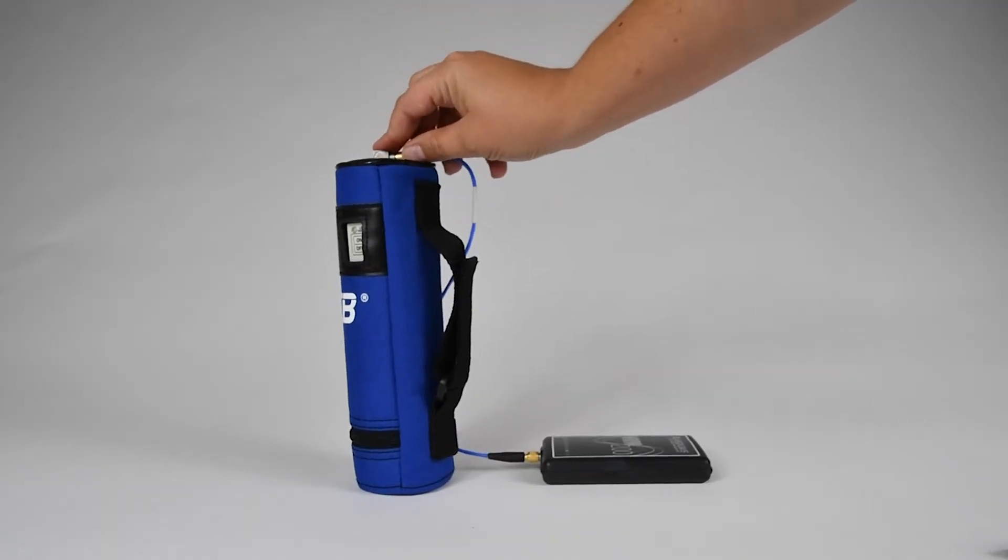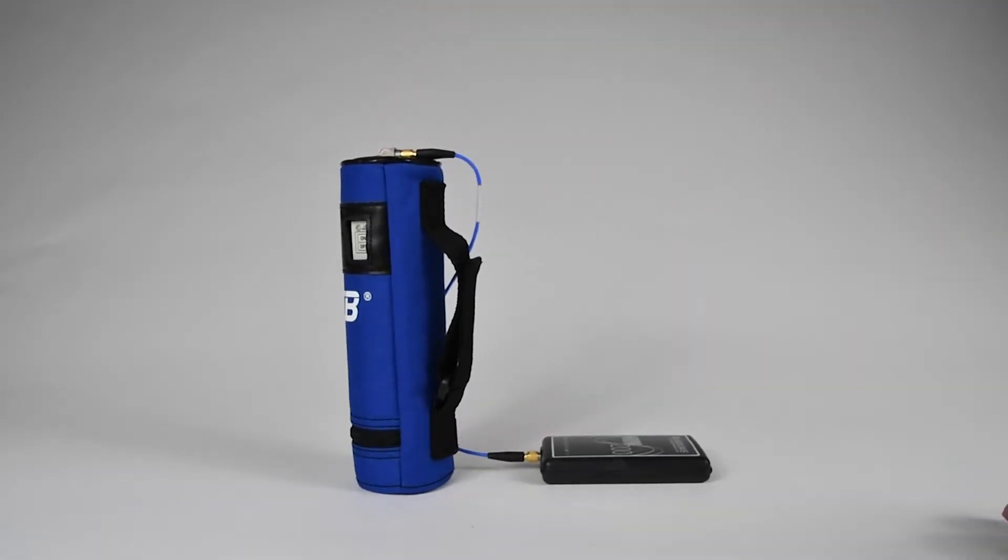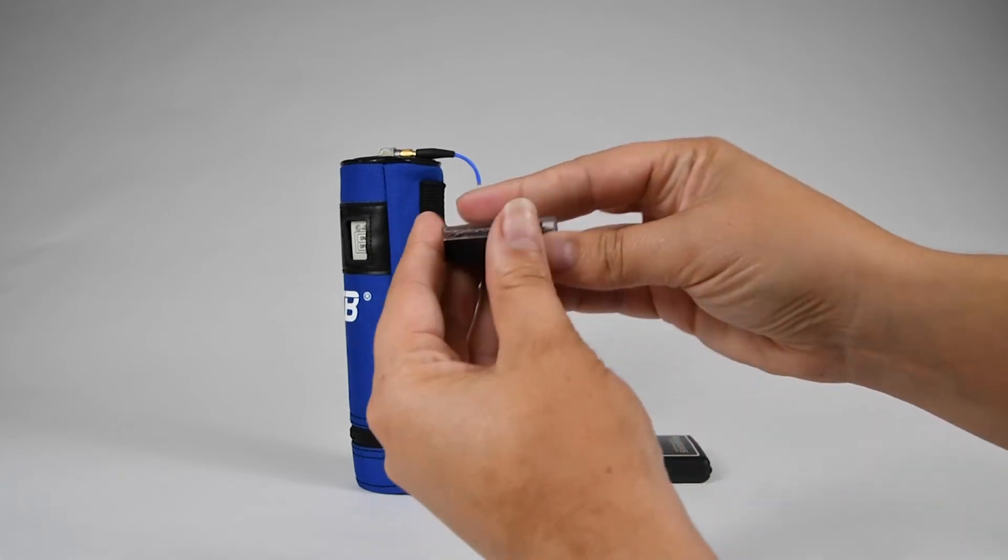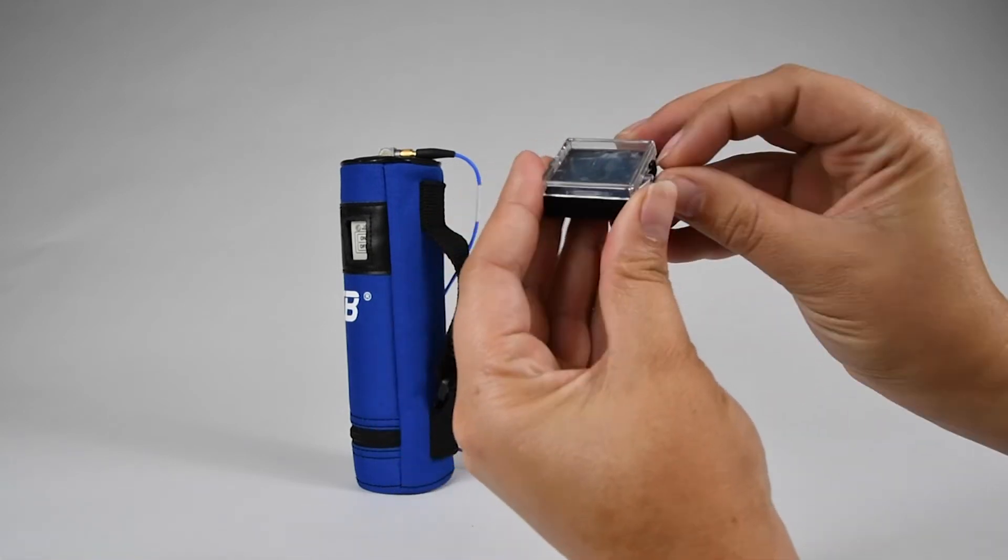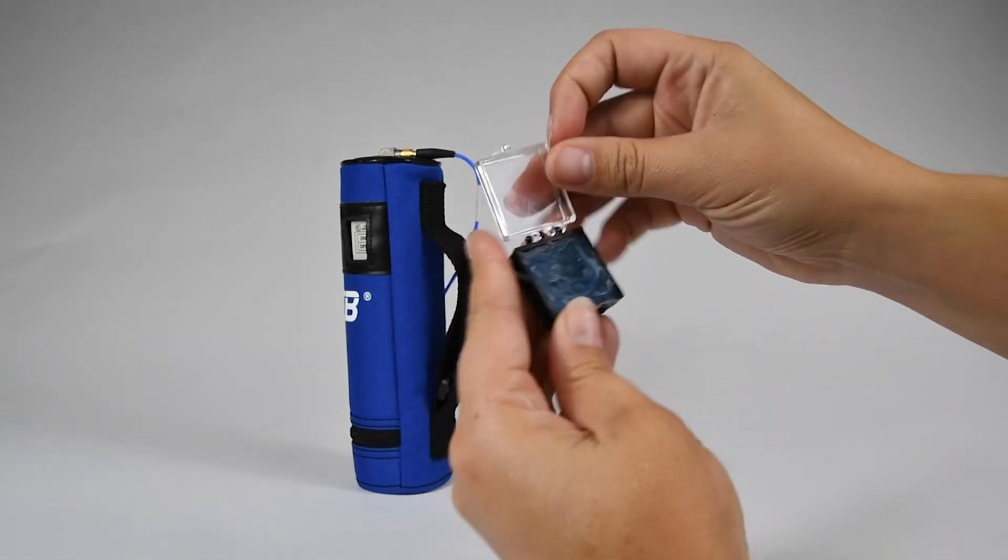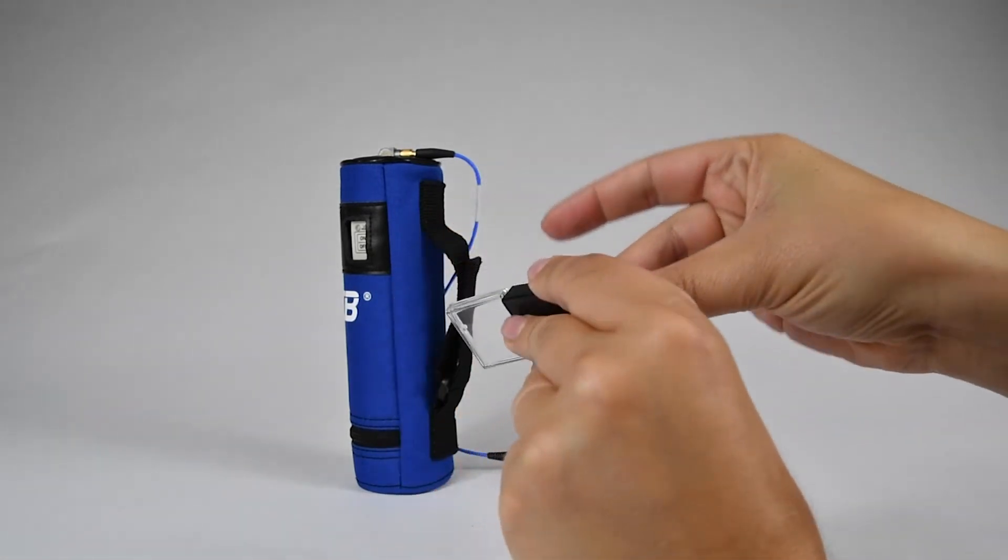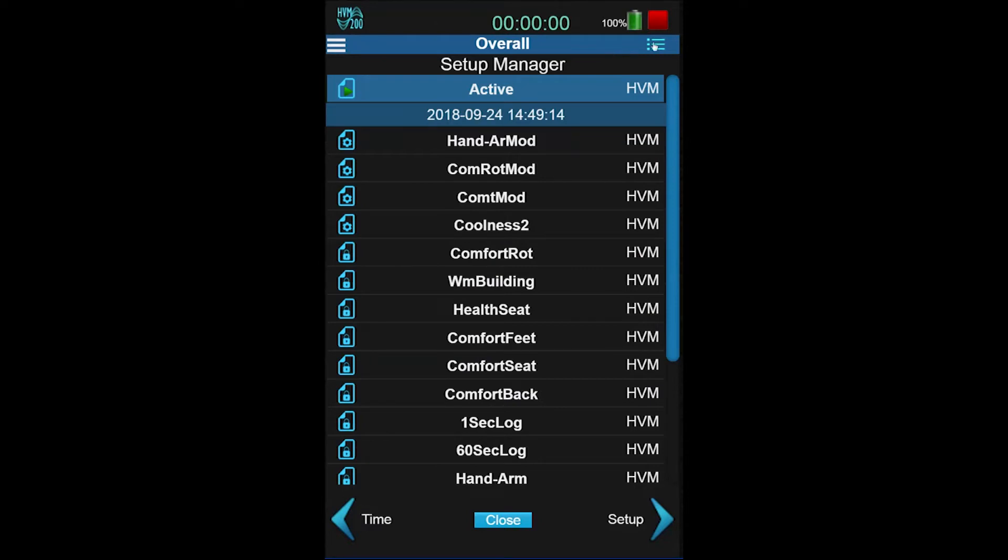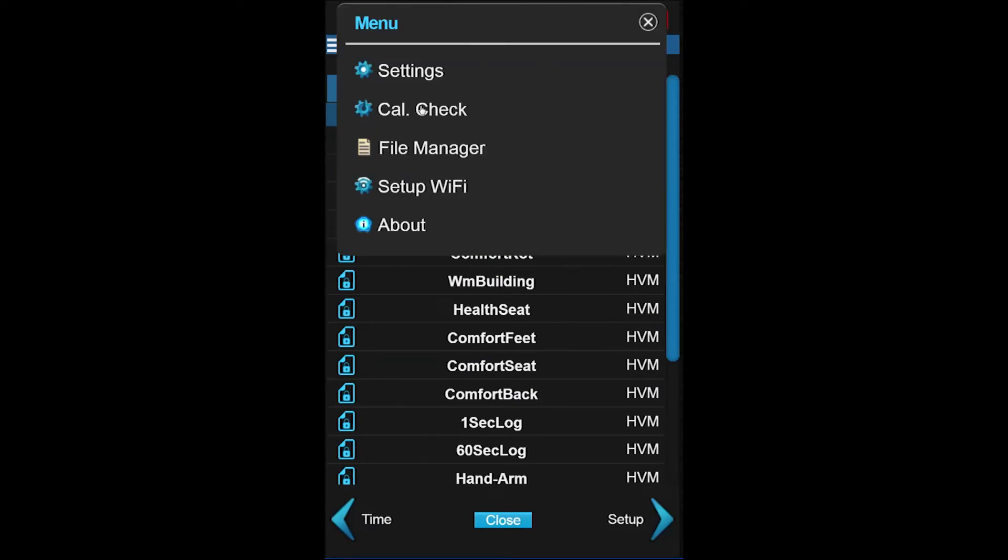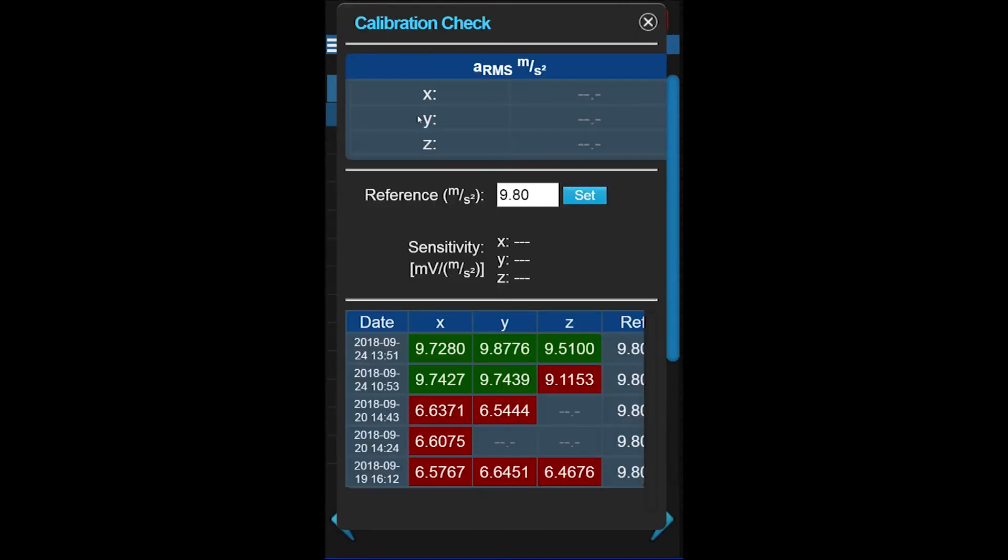Attach the transducer on your shaker so the axis that you wish to check is oriented properly. You can attach with the set screw or stick it with the provided wax. Now navigate to Menu and CalCheck.